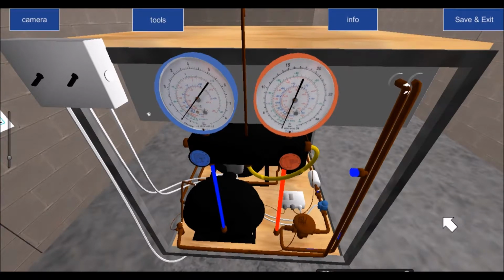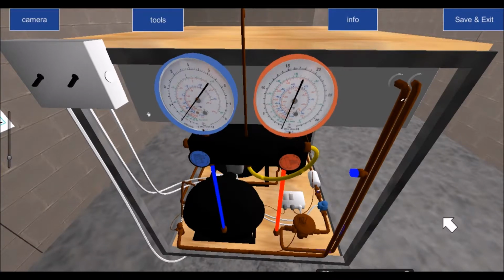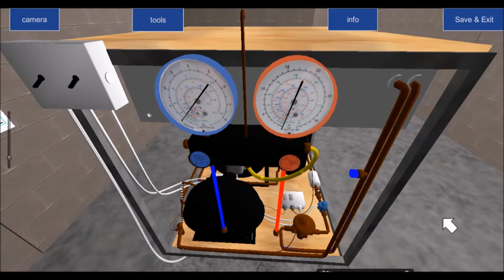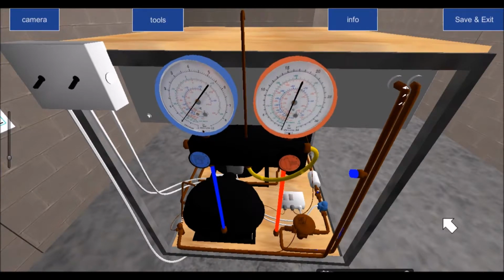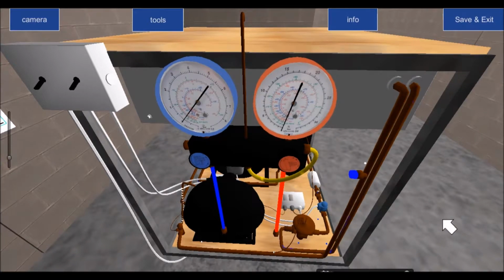There are two reasons. Obviously there's the environmental reasons, which is very important, but there's the economic reasons as well, because the cost of refrigerant is increasing all the time. And in fact, I said there were two, there's probably three, because the third reason is that every time you put the gauges on and off and let a little bit of gas out, you're reducing the charge. It might take a long time or multiple times of fitting gauges, but over time you start to reduce the charge of refrigerant. If you reduce it to a point where the refrigeration system stops working efficiently or starts to give trouble, then you have a system that's slightly undercharged. That requires you to carry out a full leak test on the system before you can add refrigerant.